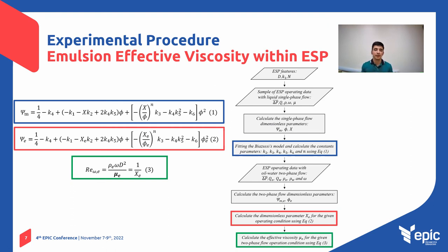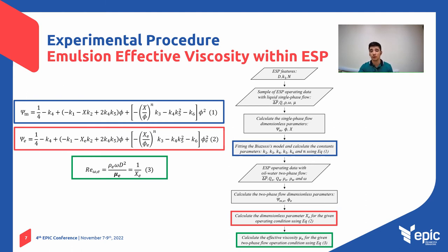An indirect method to determine the emulsion effective viscosity within the ESP was used, which was obtained from the water-oil emulsion performance curves. The viscous performance data were used to determine the parameters of a dimensionless head empirical model for the tested ESP. The calculated values were compared with the effective viscosity obtained from oil and water emulsions, as well as the ESP performance operating with emulsion and oil.